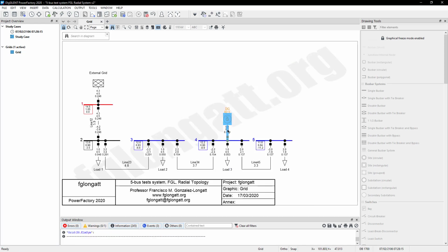Now I run the power flow. Wow, voila. Right now we have a relative load of the synchronous machine, around 82%, producing 0.8 megawatts, 0.2. However, the voltage drops. Now the voltage is 0.88 because the synchronous machine is reaching the limit.